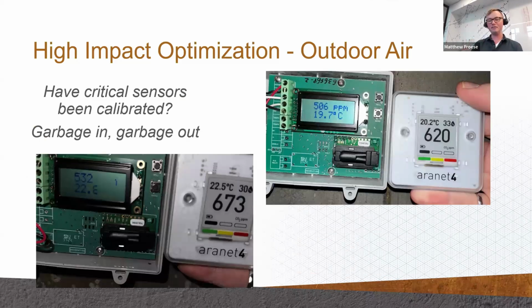And the same system, at the same time, they had new CO2 sensors put in for demand control ventilation. Neither of them had been calibrated, and they were both over 100 parts per million off. So our offset was larger than, in this case, the signal we were looking for. So with any of these systems, garbage in, garbage out is still going to be a problem. You need people who have time to go validate and to check and to notice, wow, that number doesn't really make sense. It's not moving in the way we expect it to. And then what do you do about it?